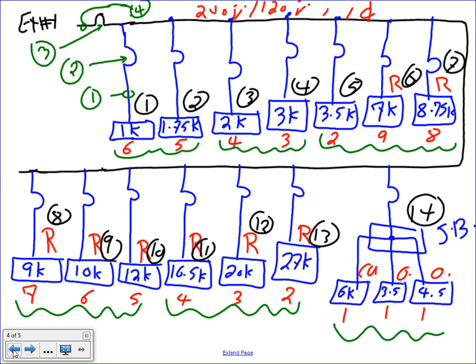So we're going to size the branch circuit. If you look at 1 and 2, they are not in the table. How do you size the branch circuits for a countertop cooking unit and oven? By the nameplate. So we're going to do the nameplate Ohm's law calculation. Chris, can I move on or no? Isn't that covered by small appliance? Ranges are a special type of small appliance. I mean the ones that are 1K. They're cooking units, but they're less, so I don't apply the small appliance rule like 1.25 and all this good stuff on them.